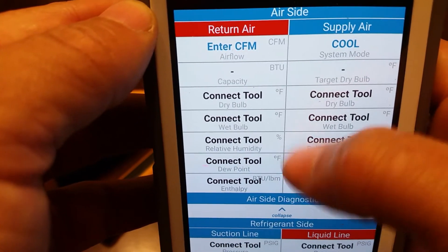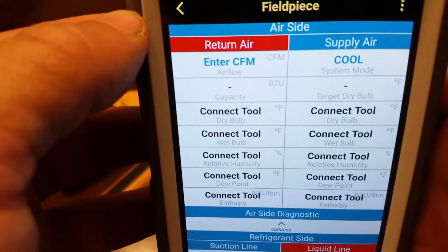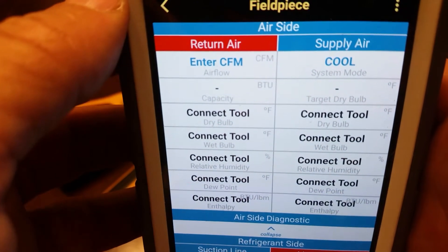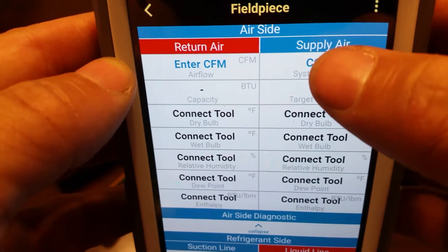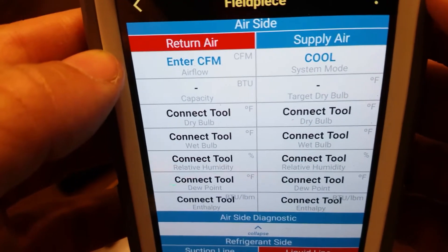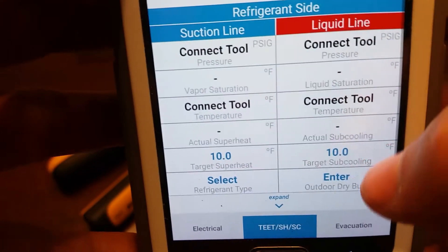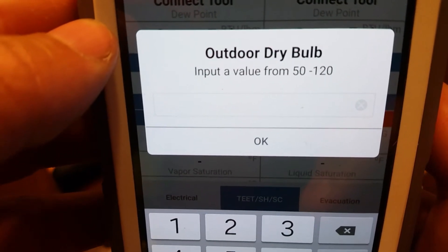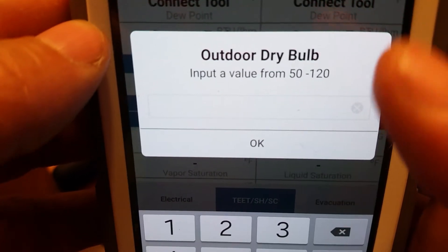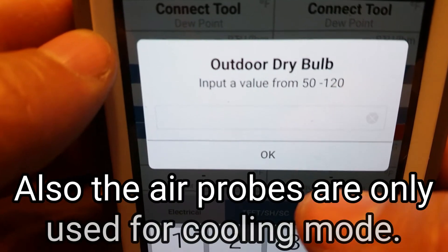This is the app. You can pull down a couple screens — it gives you the option to enter manual CFMs. Fieldpiece is supposed to come out with some type of anemometer to get that data without having to manually input. It does give you the option for system mode, whether it's heat or cool. I don't think that feature works very well. When you do go to heat mode and scroll down to outdoor temperature, every time you click it, it scrolls down a little bit farther. Your outdoor dry bulb only gives you options between 50 and 120 degrees, so if you're running heat pumps in heat mode, you're more than likely going to be well under that 50 degrees most of the time.